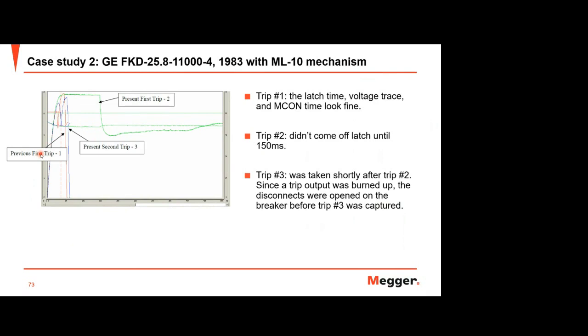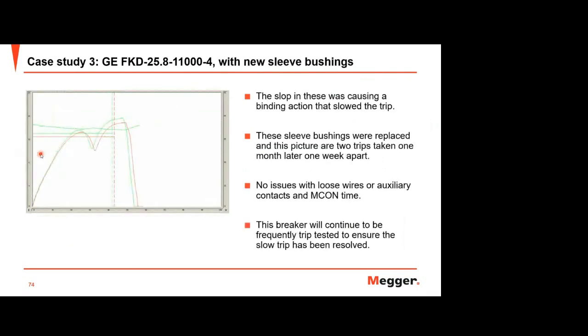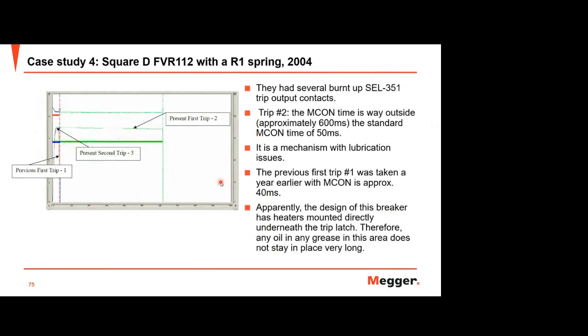Okay, and next case is another example, GE FKD25 with new sleeve bushings. So they can see the difference in the first trip before and after they replaced the bushing. A little bit here, the effect on the second peak is a mechanical issue. So there is no issue with loose wire or auxiliary contact and main contact time. So they continued to operating the breaker.